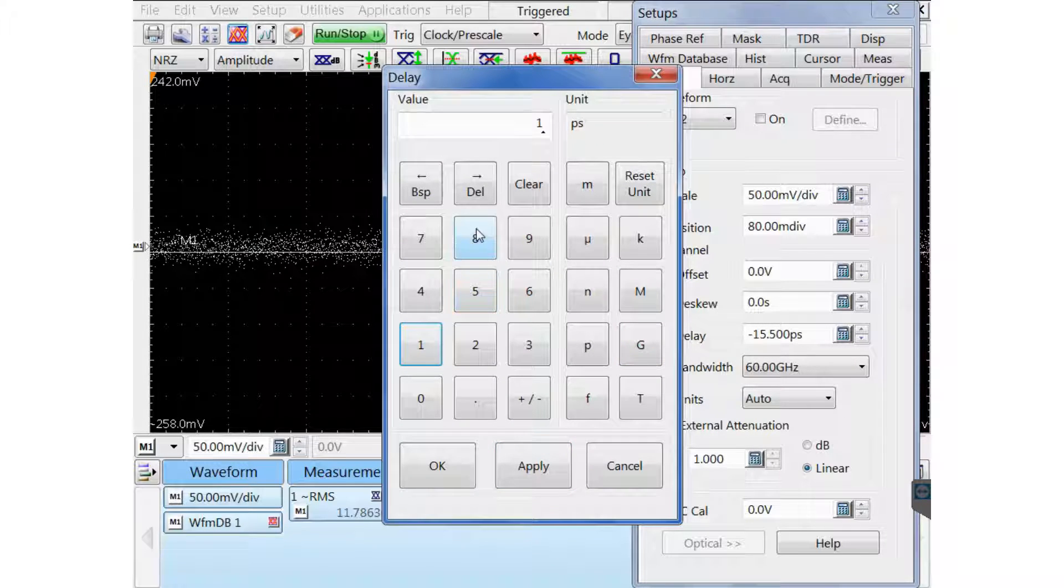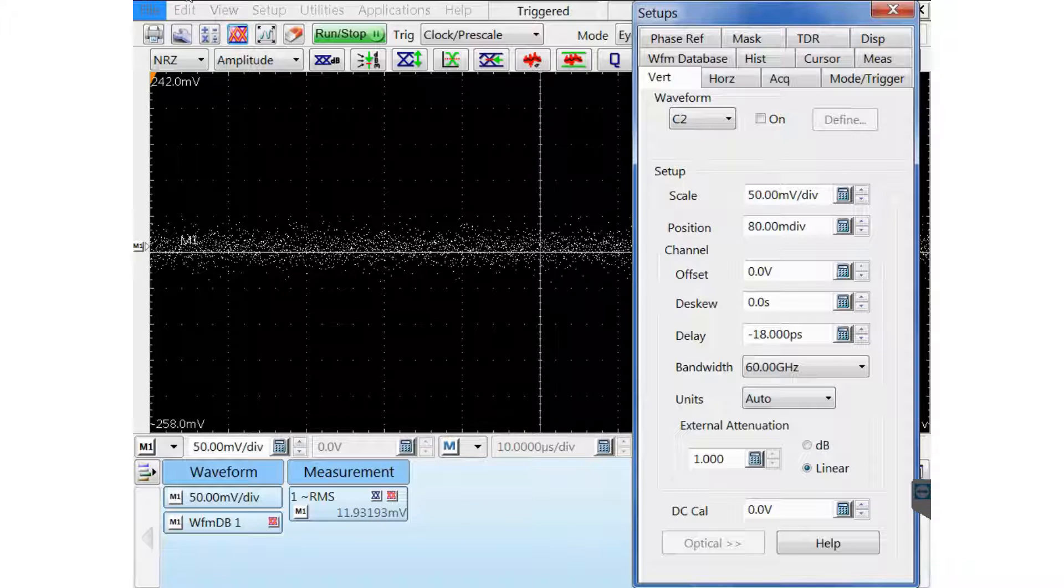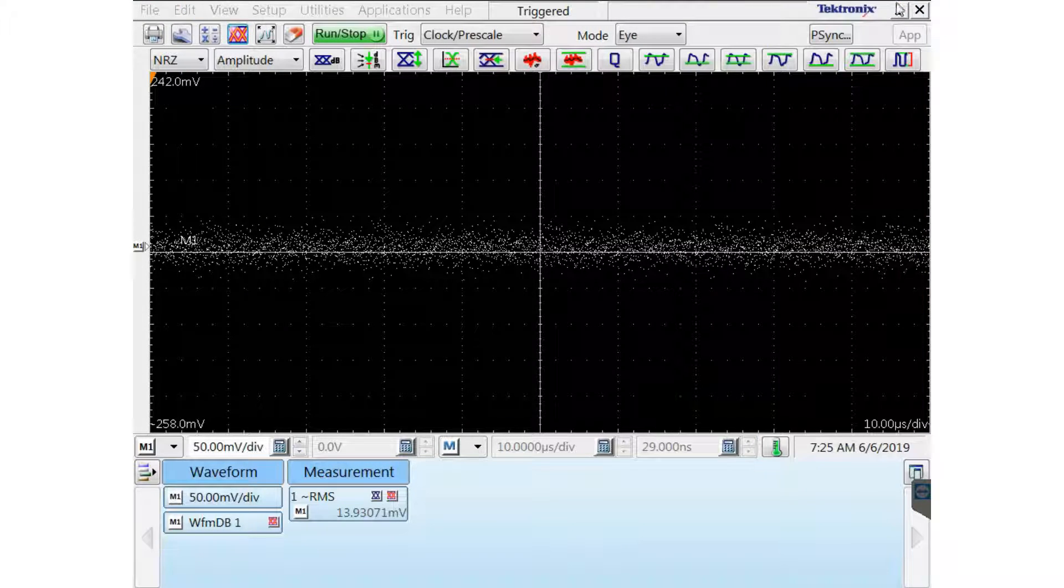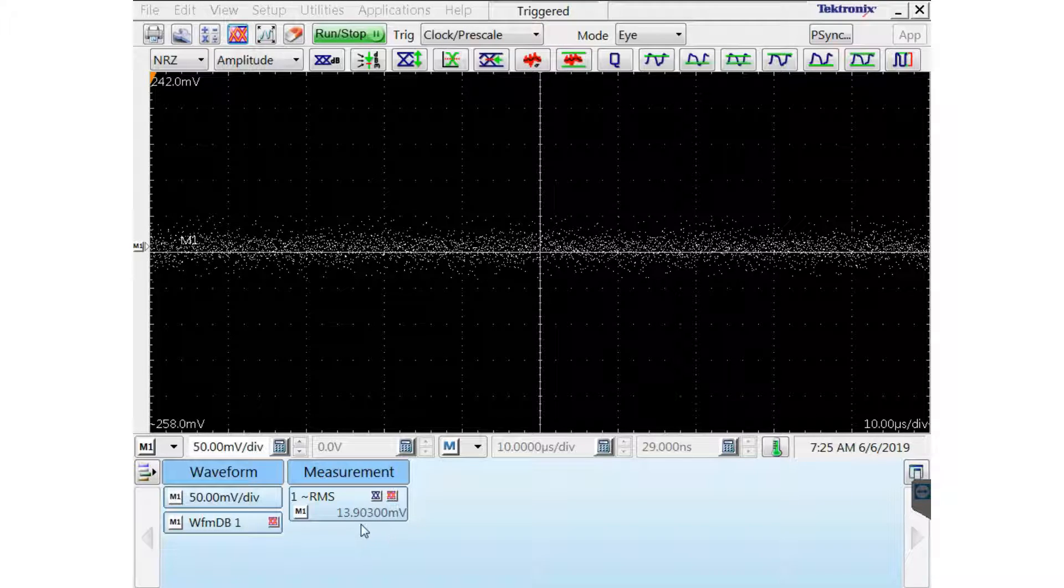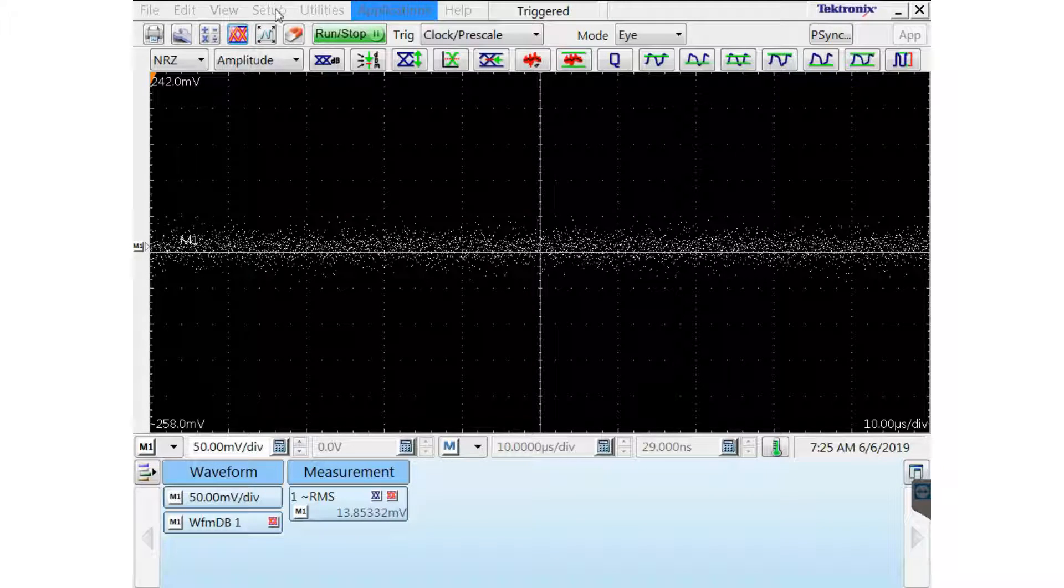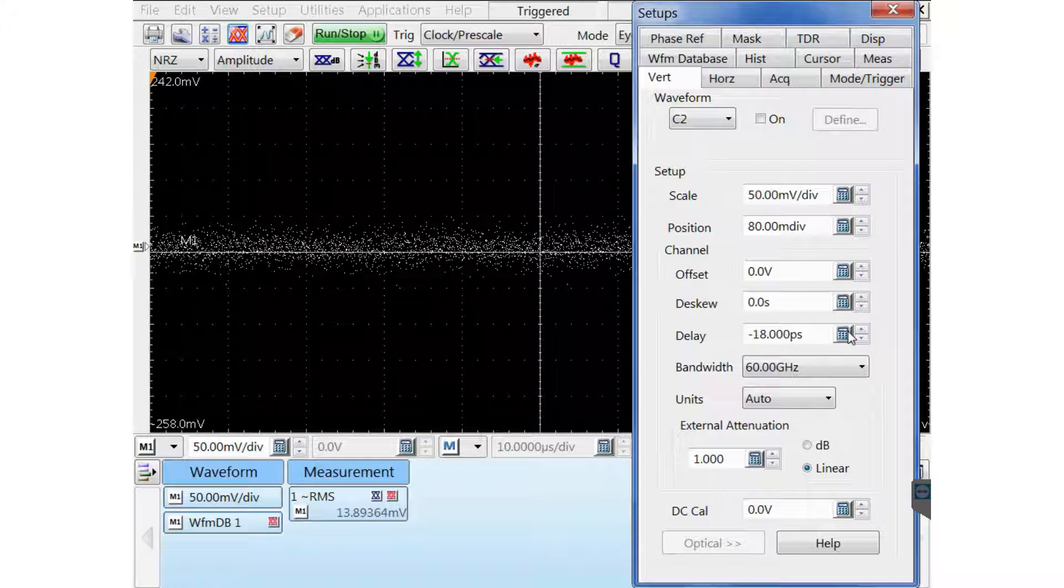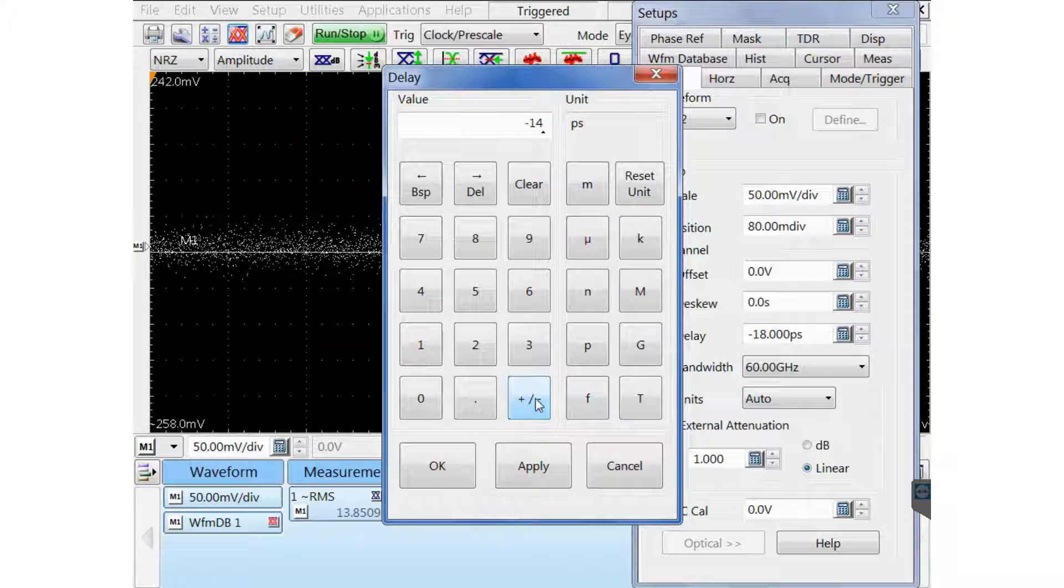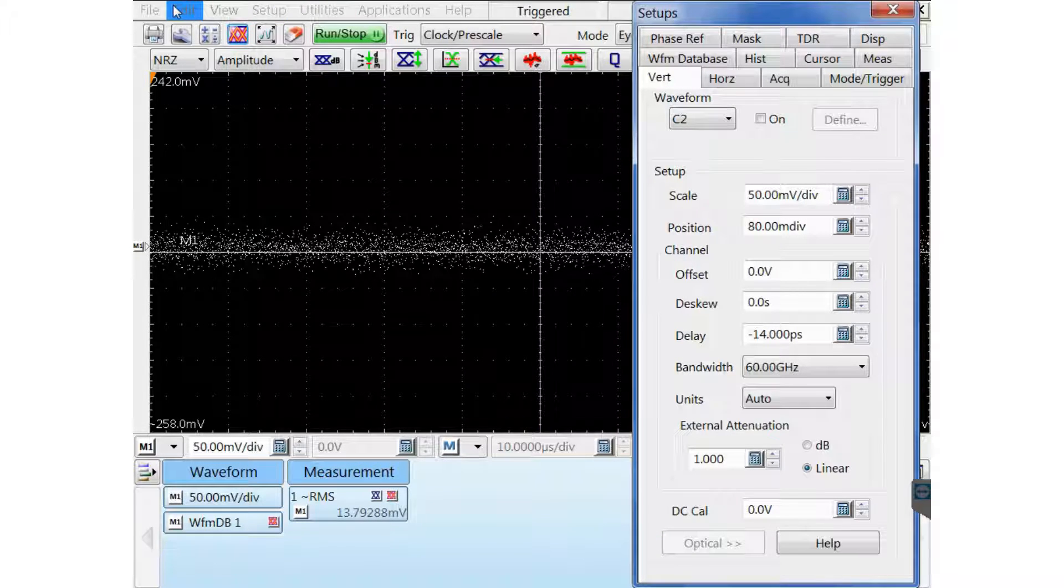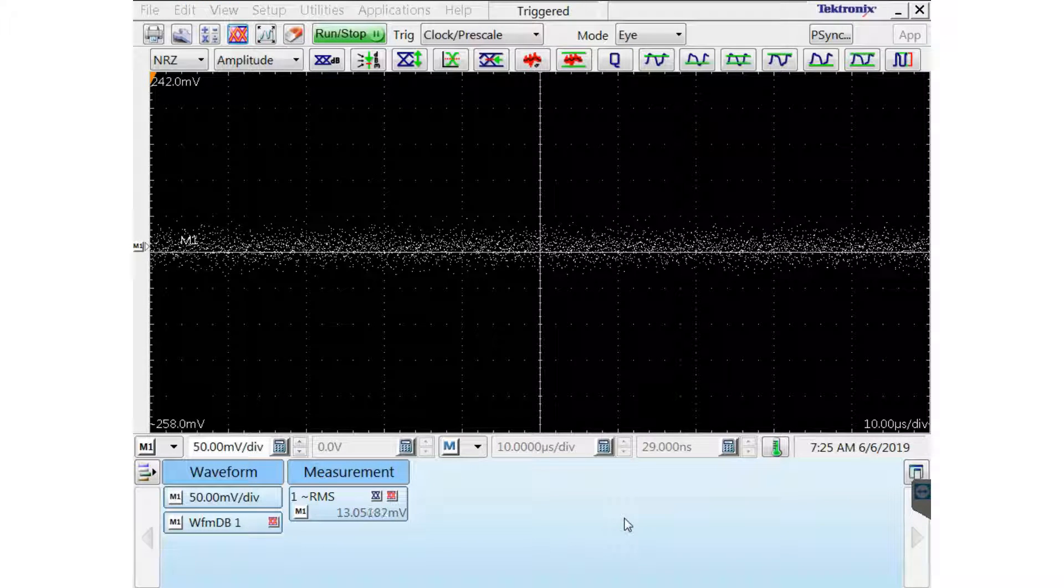So, for example, I could go back to my original starting point and enter that one. And I'll clear the data. And now I can see that my common mode voltage is higher. So that's not the best position. And then you can go to the other side. You can enter different values here. And once again, this is an alternate capability using the common mode for you to find the best position.